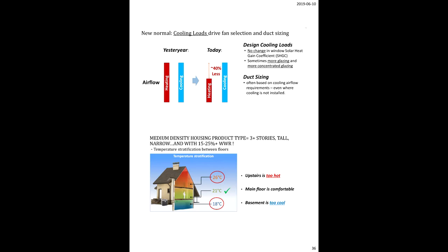Well, now that the heating loads have dropped, because you're doing all sorts of cool stuff to the envelope, and yet the window sizes are going up along with the solar heat gain, it's doing this. That's where we get ductwork that is the right size for summer, and yet too big for winter.